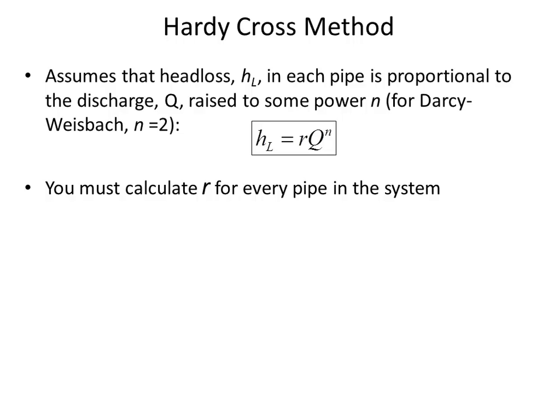The first place that we're going to start is by calculating resistance to flow through a certain pipe. The Darcy-Weisbach equation, h_f, is f L V squared divided by D 2g. We're going to transfigure that a little bit so that we can use it in the Hardy-Cross method, and we're going to group together some things that aren't going to change, regardless of what the flow rate is.